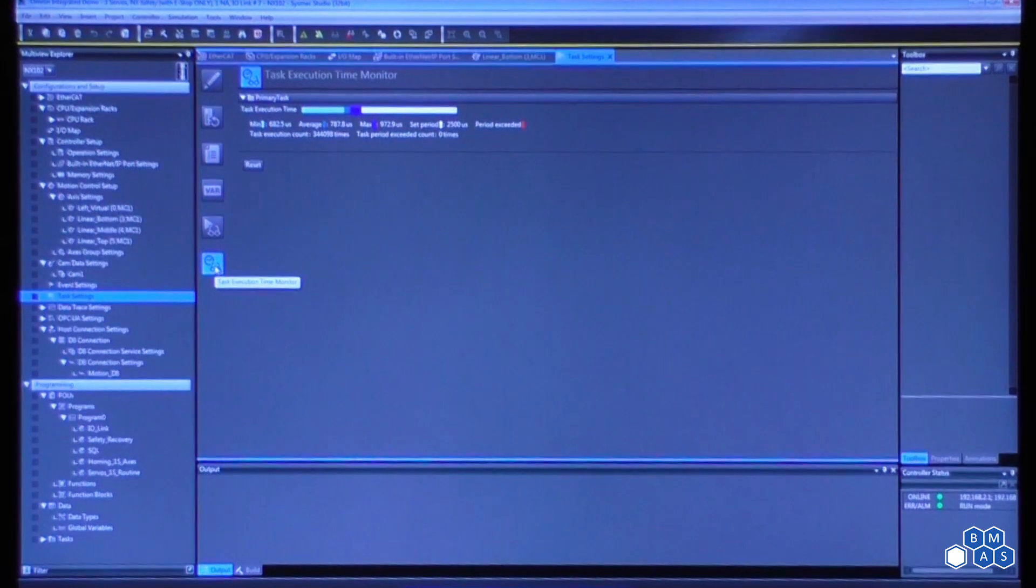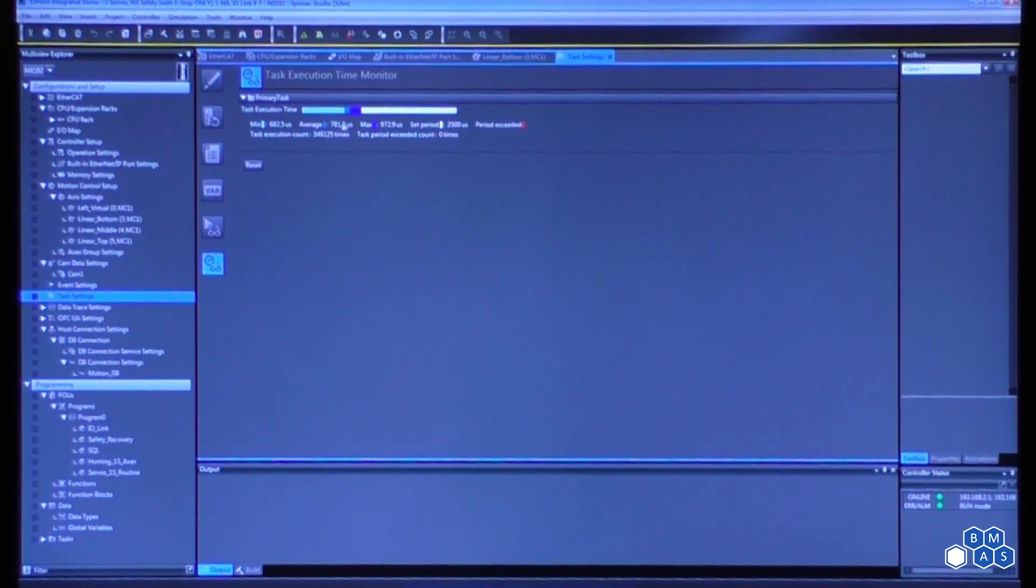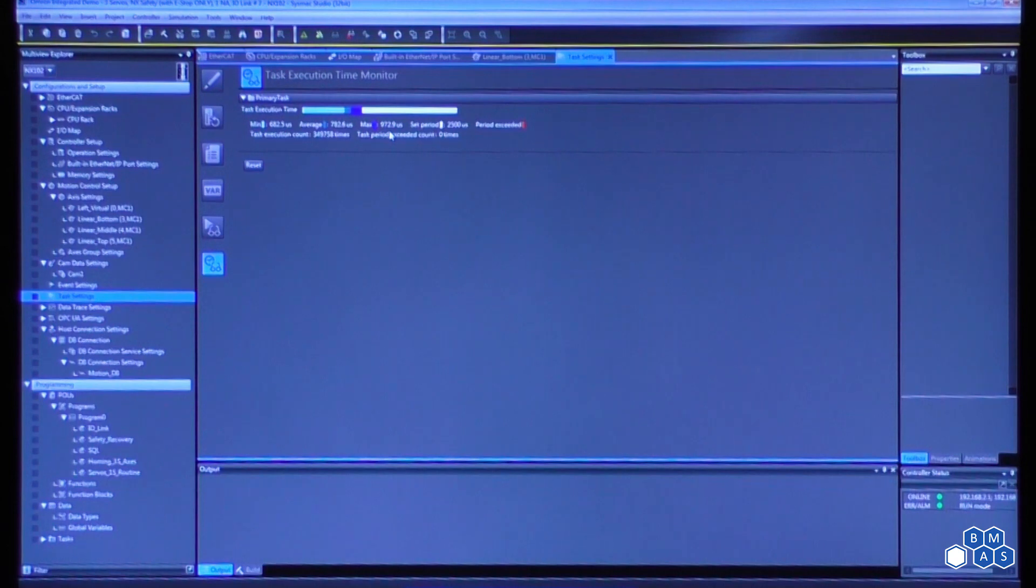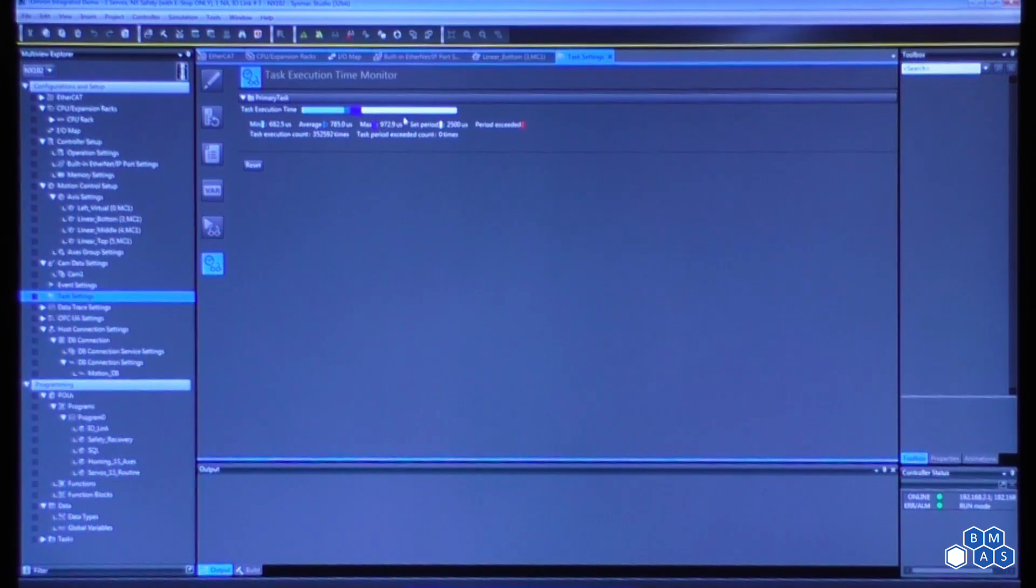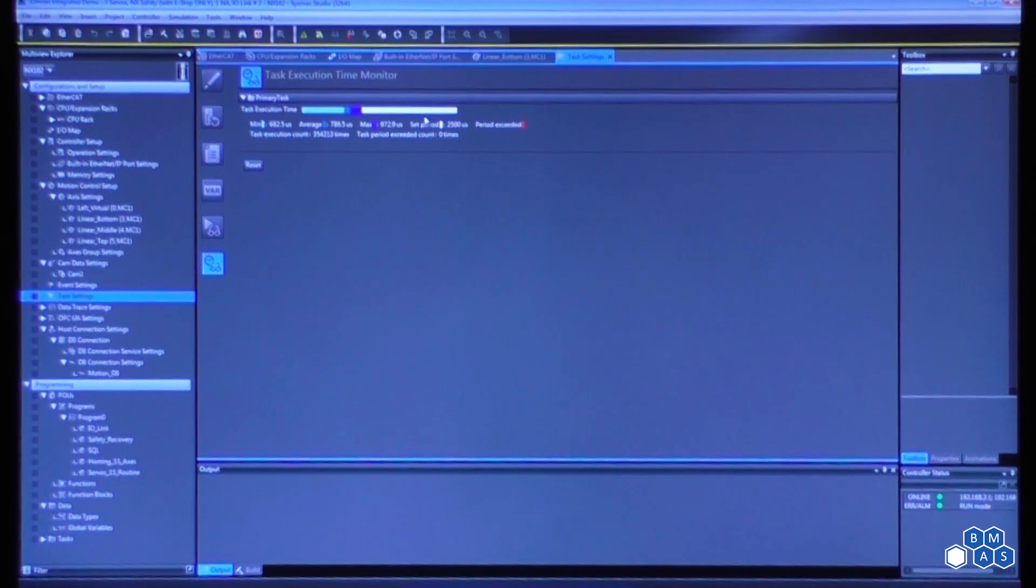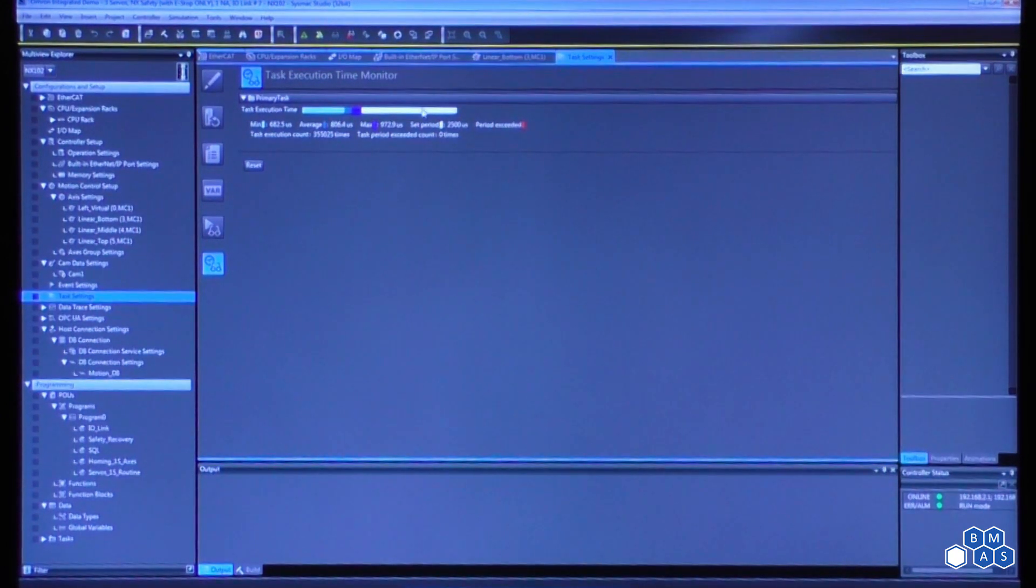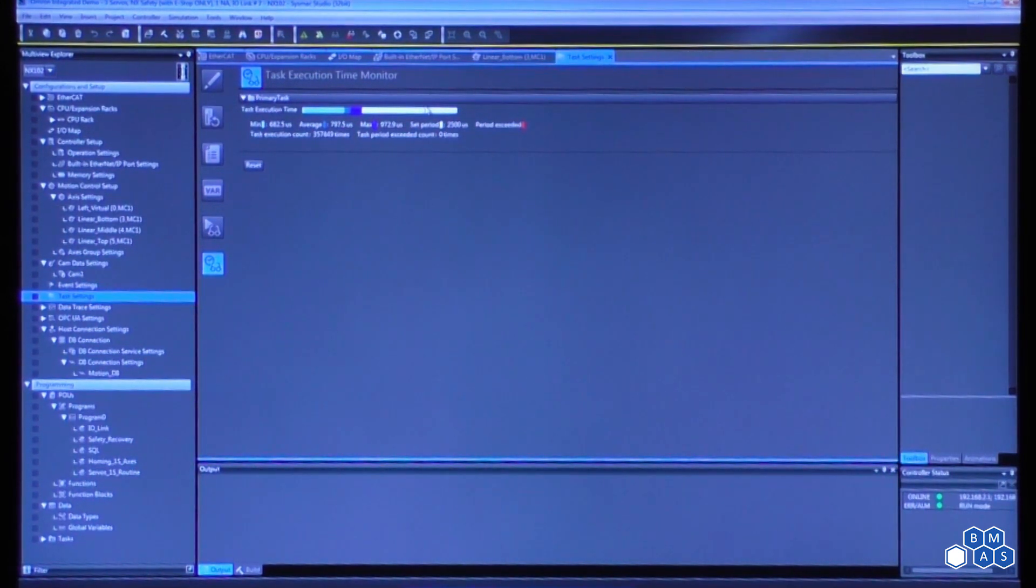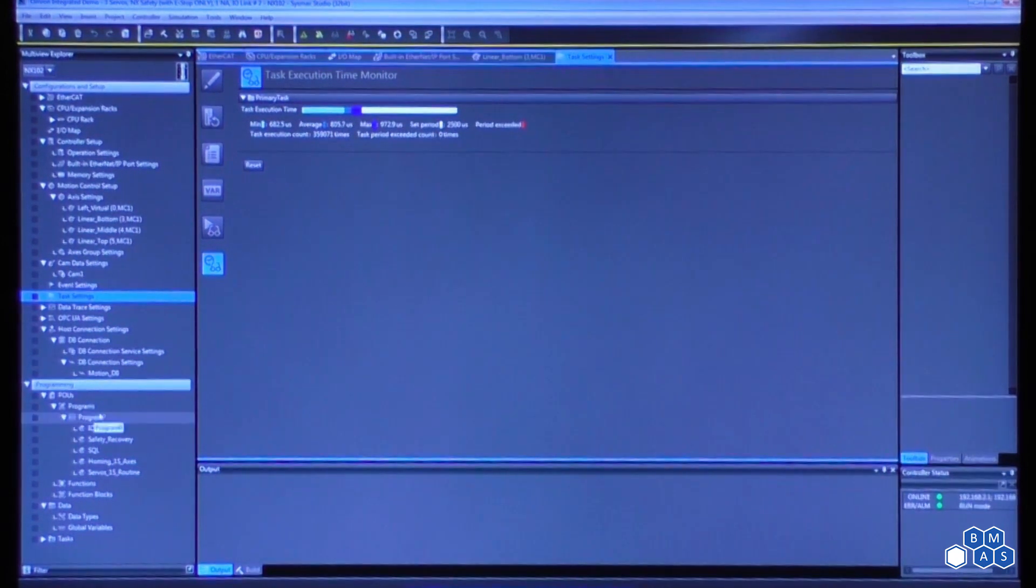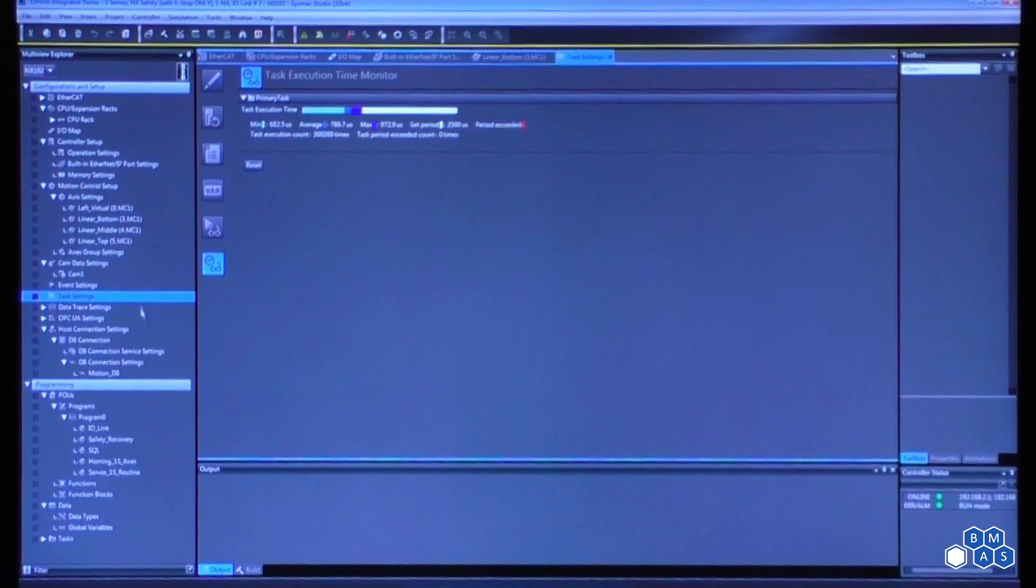So the last item I want to show here in the task settings is what's called the Task Execution Time Monitor. So this is a means to identify what the average scan time is of the processor. In this case, it's 780 microseconds, and the maximum scan time was 972 microseconds. So with a 2.5 millisecond ceiling scan time, we're in a very comfortable spot right now. Realistically, when we get to, we'll say 80 to 90% of that maximum scan time—and this is kind of dependent upon the processor type that you're using—but once you reach that threshold, that's where you might want to consider creating a secondary program that would handle lower priority tasks.